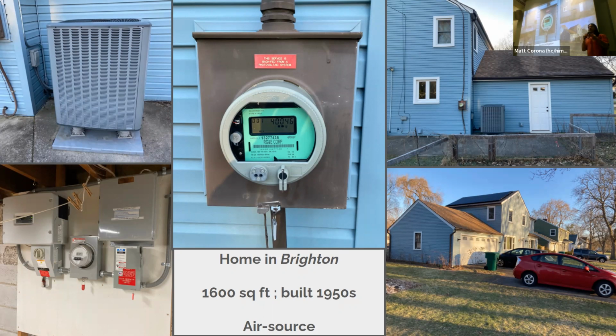You can do a hybrid system — it's possible, but I wouldn't recommend it. There is one scenario where it makes a lot of sense: if you have a relatively new gas furnace or other furnace, it wouldn't make sense to replace it. You can install a cold climate heat pump to do the majority of the heating and cooling, and use the furnace as an air handler instead of installing another unit in your basement for the air source heat pump — basically using the furnace's fan to distribute the air. That way you can save a little money on installation if you have a relatively new gas furnace.